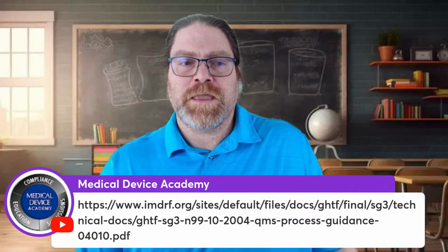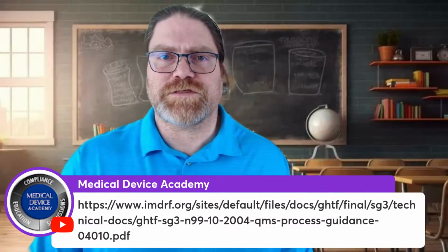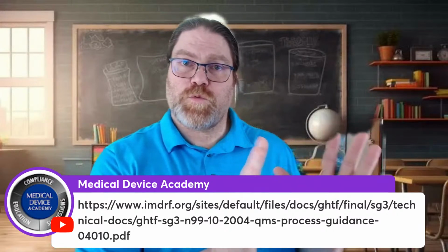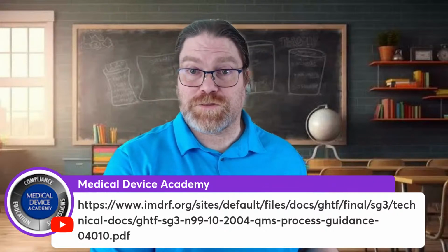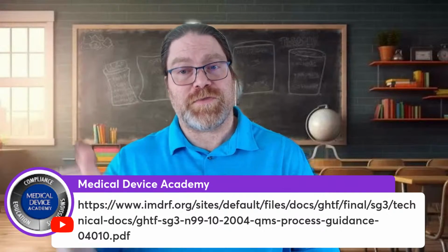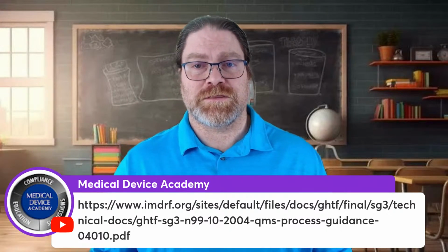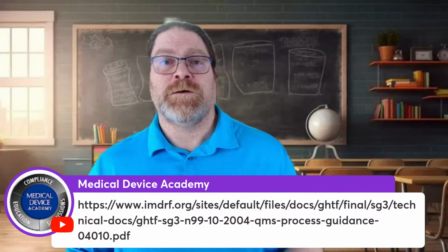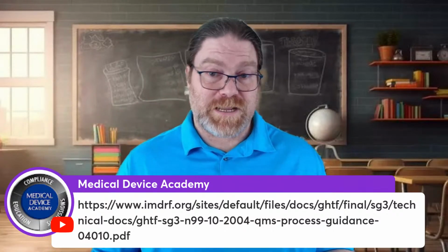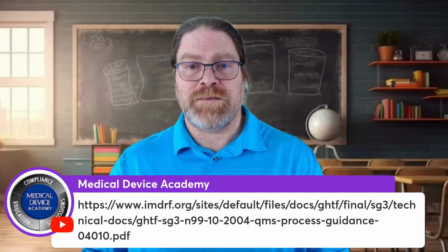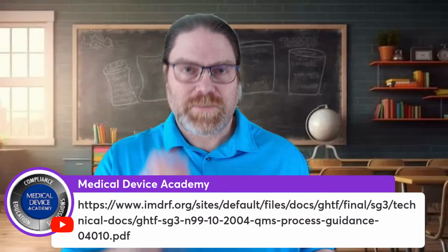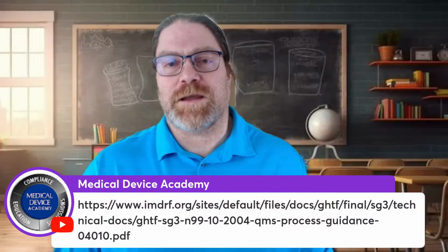and so then you can edit it to be your own. And if you're looking for what the FDA wants for a submission, when you have a report, typically you have, here's what our plan was, our predetermined acceptance criteria. That's one of the things they're looking for in your protocol. And then you have your report that has the actual data and summary and conclusions. Some companies combine the two together. They'll have a report with fill in the blanks and a place for collecting the data, like a data table. And so when they fill it in, the blank form becomes a record or a report.